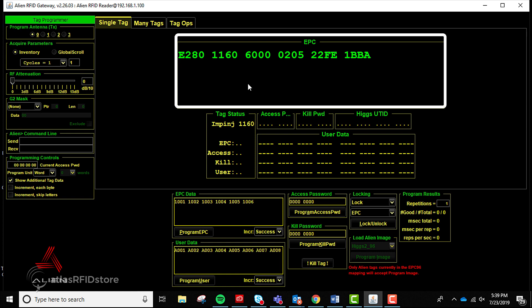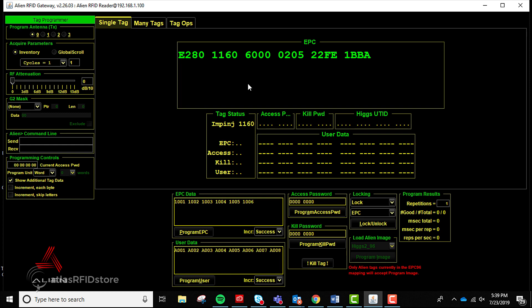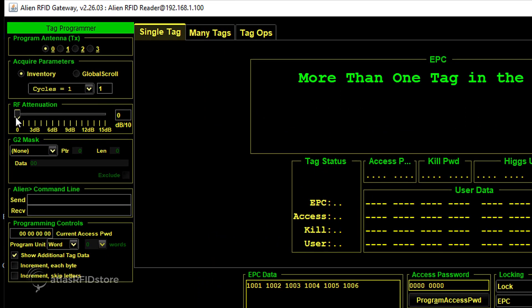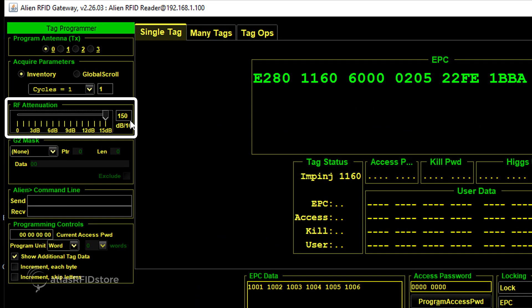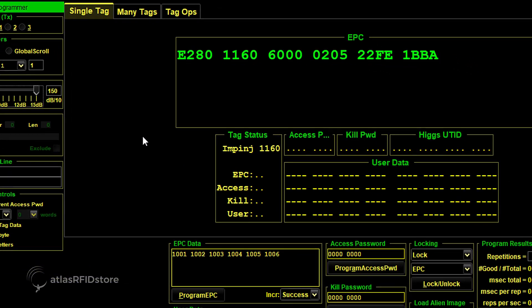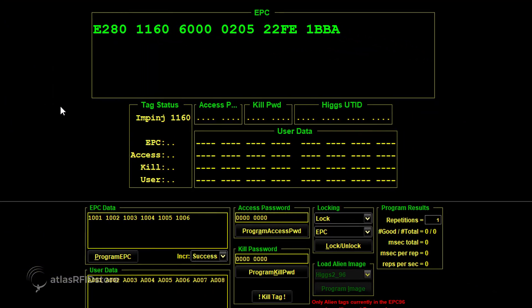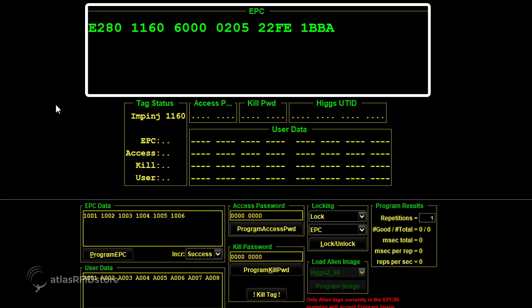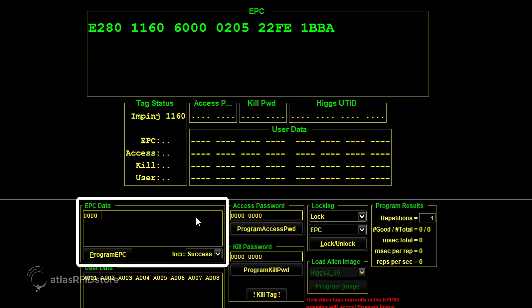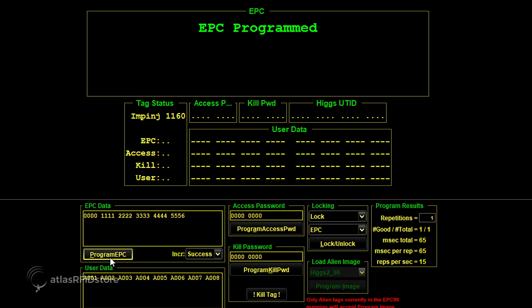As you can see, we have one tag in the read zone, and the EPC number is shown here. In order to only read one tag in our read zone, we have actually turned the RF attenuation to 15 decibels, as you can see in the left-hand column. Now we are going to reprogram this tag's EPC number from the one shown above to the one on the screen. Using the EPC data box, we can just type in the desired EPC number and click Program EPC. And as you can see above, our EPC number has changed.